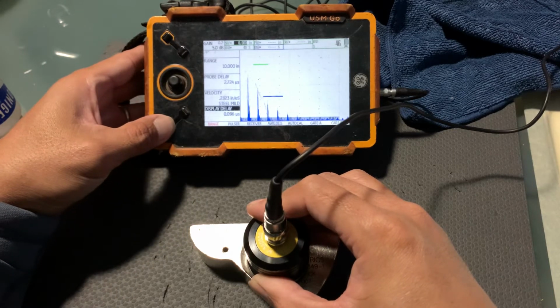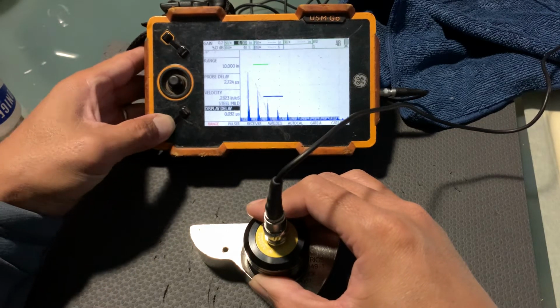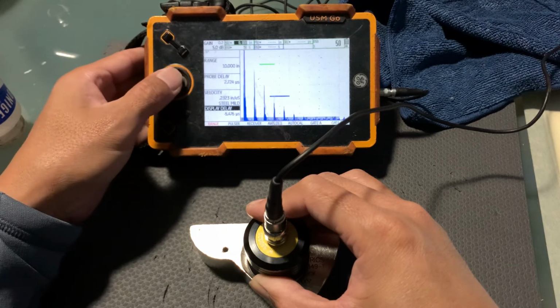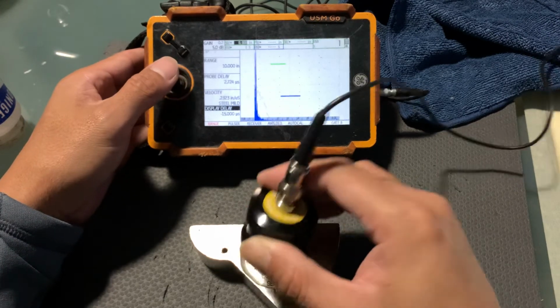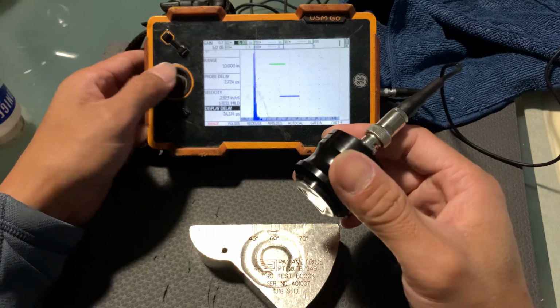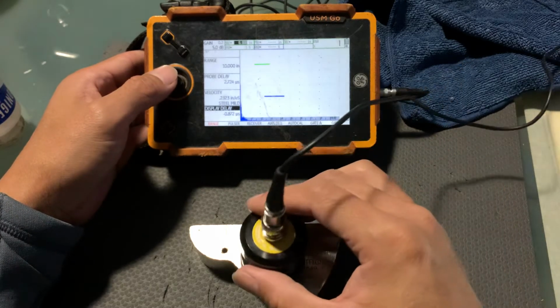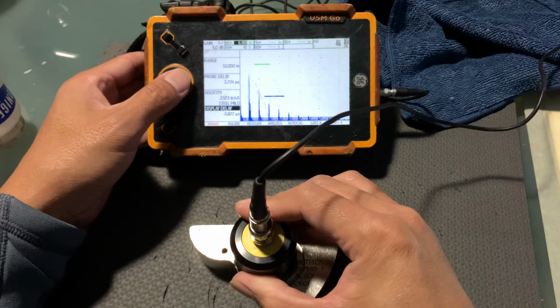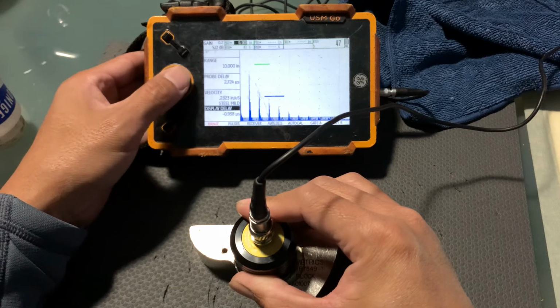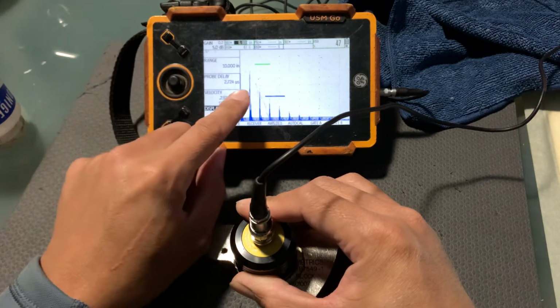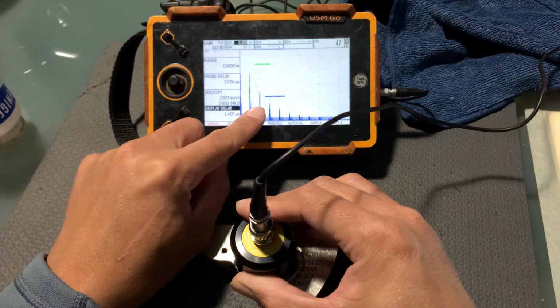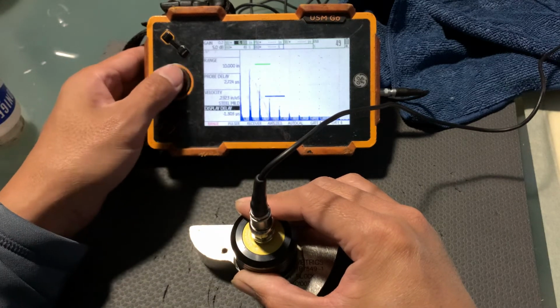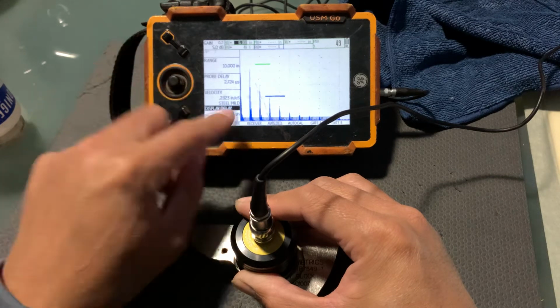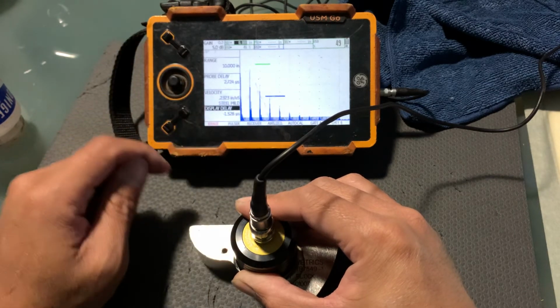We go to the display delay, move that over a bit. So I'm taking that back off. See, that's the initial bang there. Bump that over. And now I'm going to move my indications until I get a 1-inch back reflection. And that's what you see there. 1, 2, 3, 4, 5, 6, 7, 8. I got 8 of them moving over just a little bit, so every single one lines up on the 1-inch mark.